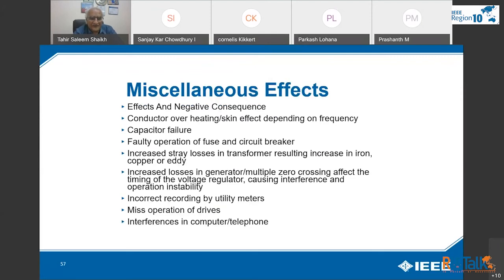breaker, increased stray losses in transformer resulting in increase in iron, copper, and eddy losses, increased losses in generator, multiple zero crossing effect, the timing of the voltage regulator causing interference and operation instability, incorrect recording by utility meter, that is very important, misoperation of drives, interference in computers and telephones.